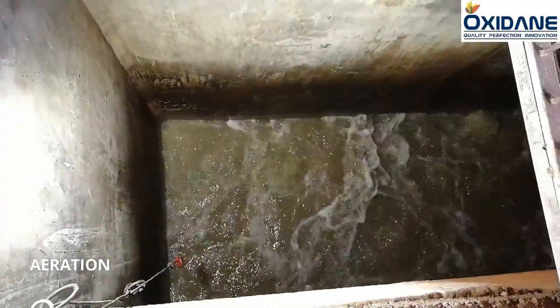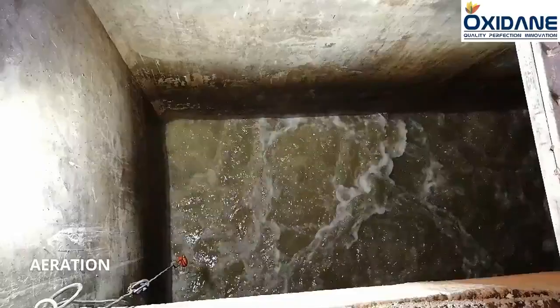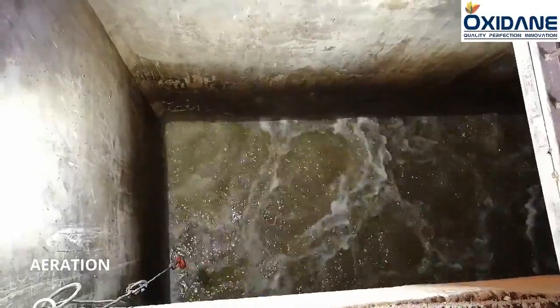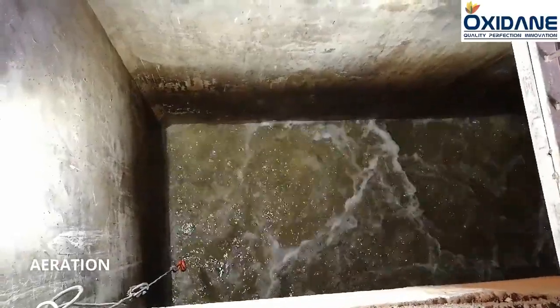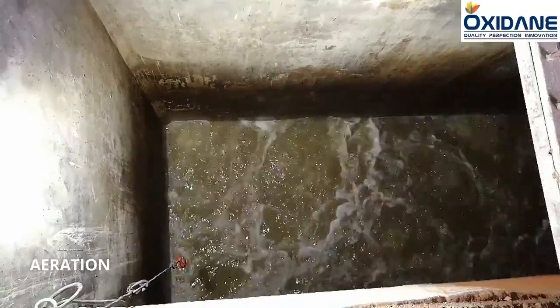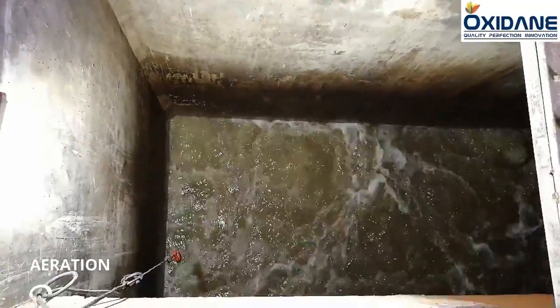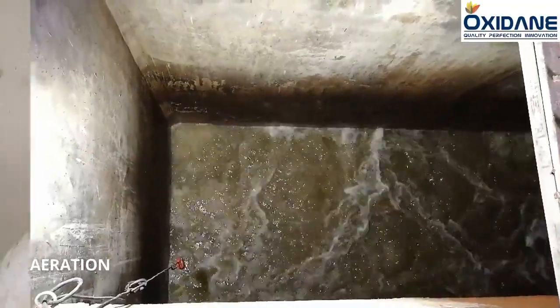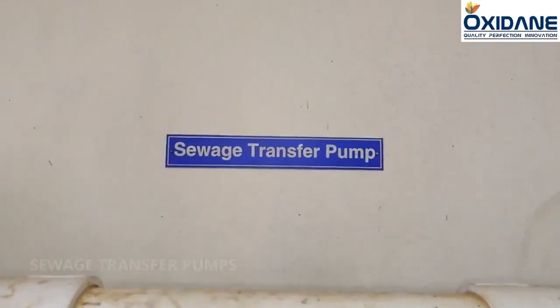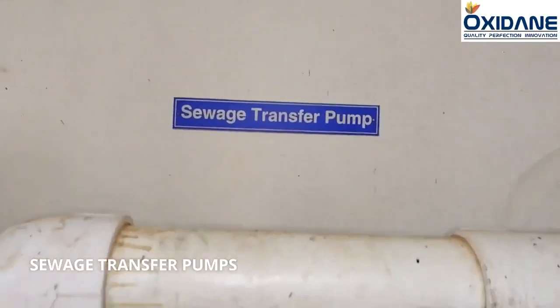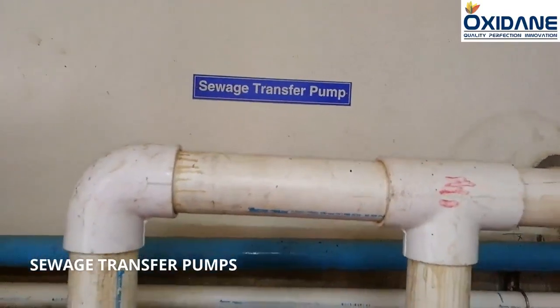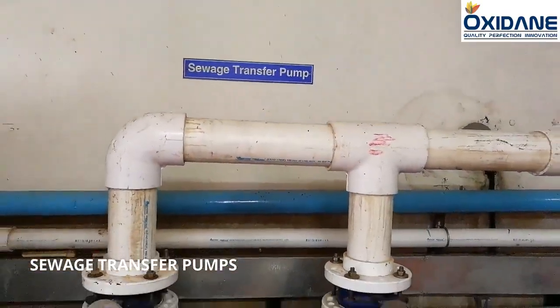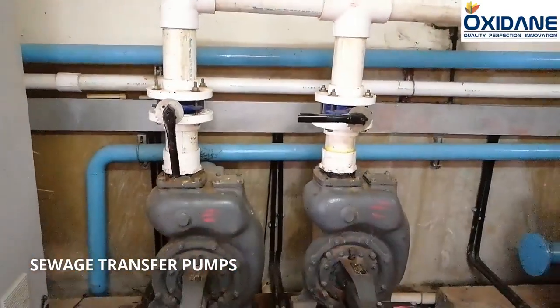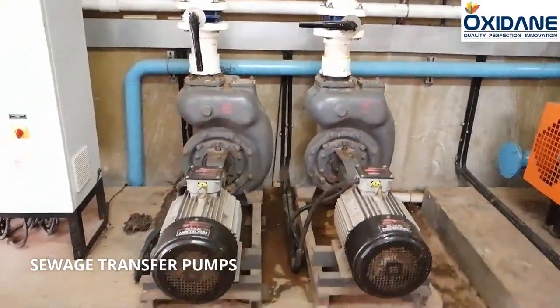OCM chemical is added into the tank every day. This chemical is added to control the odor generated from the tank. After sewage water reaches a certain level, it is lifted through a set of sewage transfer pumps. Sewage transfer pumps are used to lift the sewage water from the equalization tank to the SBR tank. Here one acts as a standby while the other is in operation.